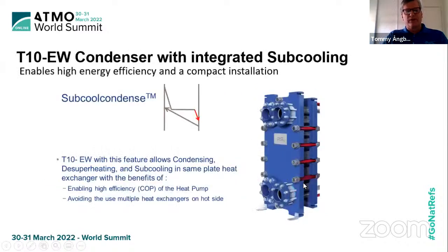So this we developed on the T10 EW size condenser, and we call it subcooled condenser. What you can see here is a temperature graph, with the heated air, and here we have the superheating, condensing, and subcooling of the ammonia, just showing that this is done in one plate heat exchanger. So it's enabling high efficiency of the heat pump and avoiding the use of multiple heat exchangers on the hot side. And this is now a top seller when we talk about hot side heat exchangers for ammonia heat pumps.